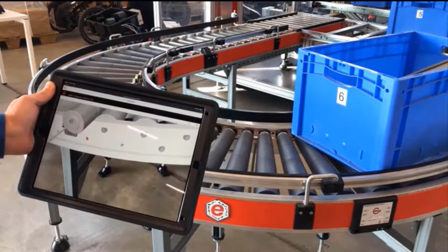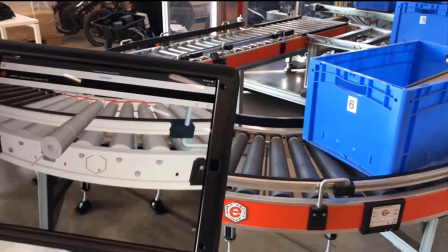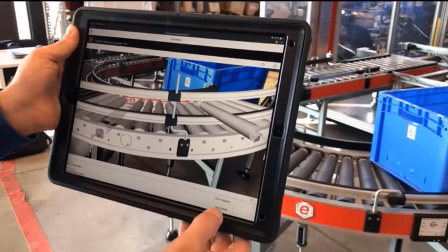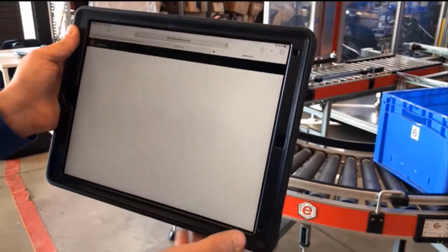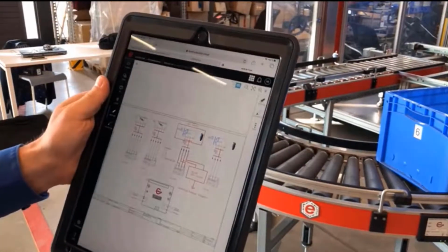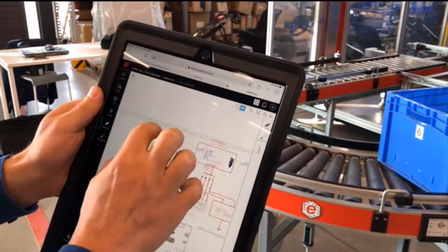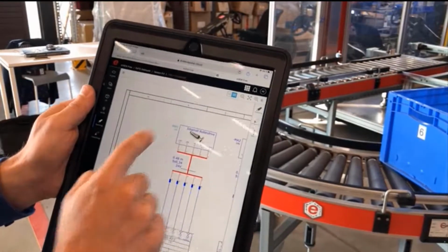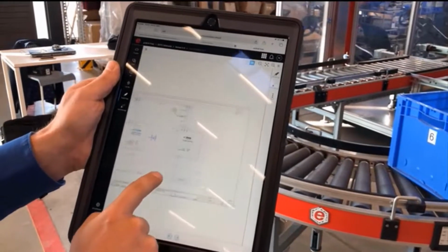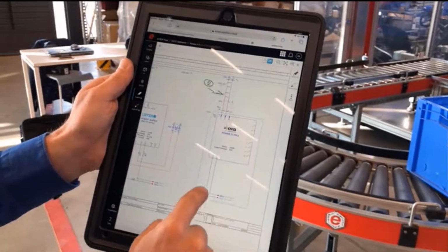Using Eplan eView and our augmented reality application based on PTC technology, the technician gets access to relevant mechanical and schematic information of the motor. The technician now analyzes the electrical path from the motor to its connected devices. To understand why there is no power to this motor, we take a look at the power supply in the schematics layout and spot the motor protection switches.